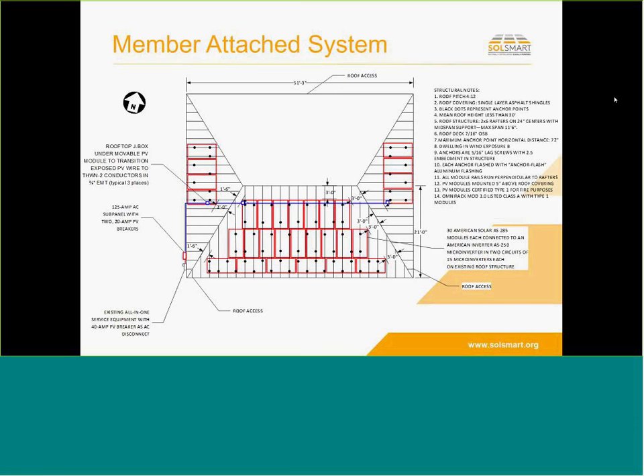Is it the heat that's generated? Well, the voltage rating is the issue with PV wiring. PV wire is an exterior cable similar to USE wire, and it typically has a 90 degree C rating, and it's rated for 2,000 volts. Those in combination make it required for systems above 600 volts, and it's used at 600 volts and below because of other concerns, like the 2014 code may suggest that we need PV wiring for ungrounded systems. If we classify a system as ungrounded, then PV wire would also be used. So it's very commonly used and probably the most common exposed cable in PV.